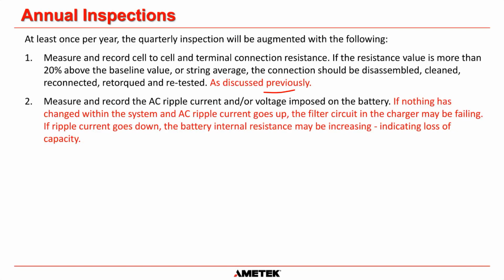And then measure and record the AC ripple current and/or voltage imposed on the battery. Now that's coming from either the battery charger or the UPS. And if nothing has changed within the system and the AC ripple current goes up, then that probably means that the filter circuit in the charger may be failing. The capacitors may be coming to their end of life.